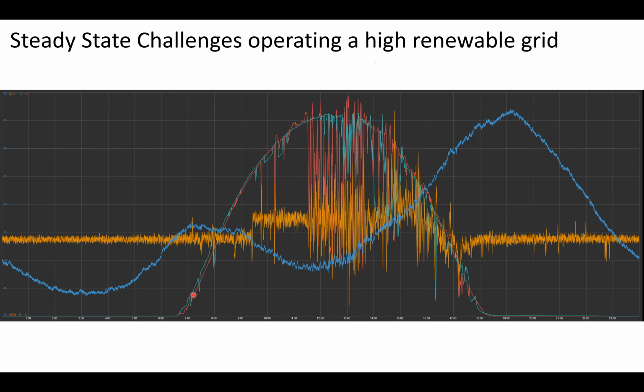And you can see when they start up in the morning, we didn't have a lot of clouds and frequency was doing pretty good. It looks like right around 9:30 in the morning, frequency was set point a little higher than 60 hertz. And I think that's probably due to trying to stay above and be proactive so that when frequency does drive down, we're not having a lot of fast frequency droop responses when frequency goes low.